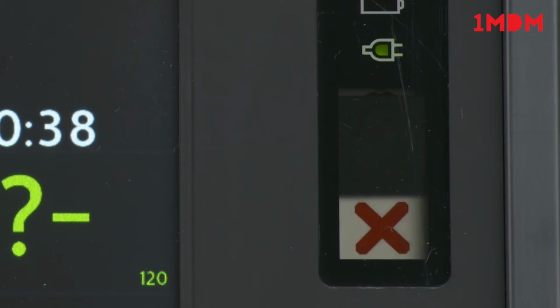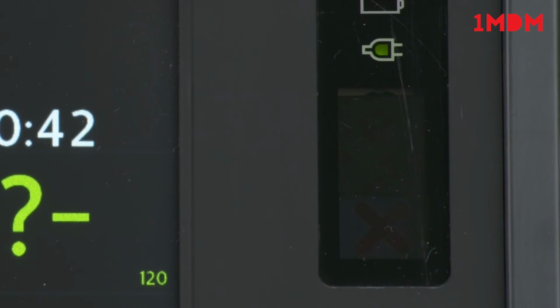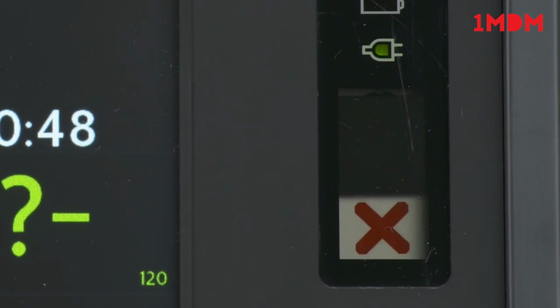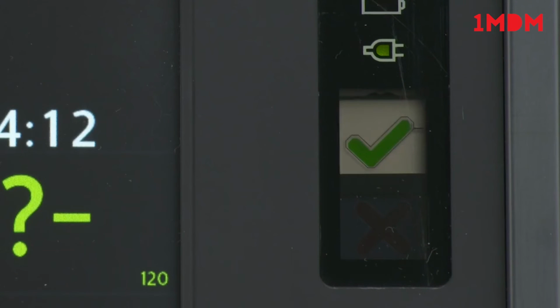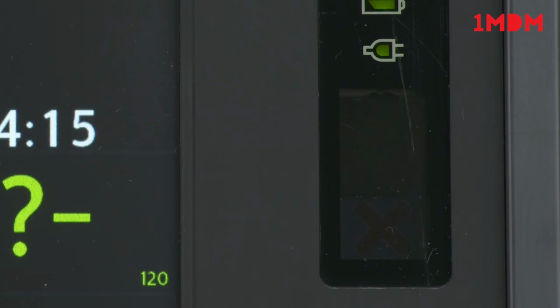A blinking red X, without a periodic audio chirp, indicates a low battery power condition, but the battery is currently charging. The device can be used, but its battery-only operation time is limited. A solid red X and a periodic audio chirp indicate a critical failure has been detected that may prevent the delivery of defibrillation therapy, pacing, or ECG acquisition. A solid red X without a periodic audio chirp indicates either there is no power available or the device cannot power on. If, after power is supplied, the indicator reverts to the blinking green check mark, it indicates the device is ready for use.